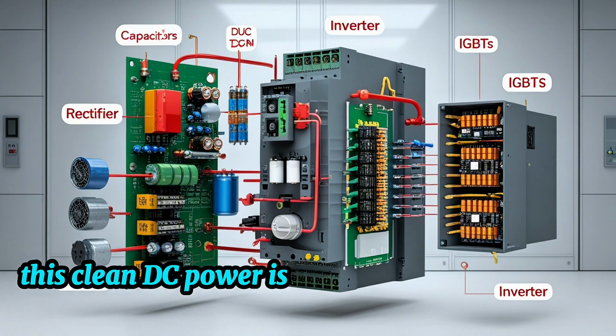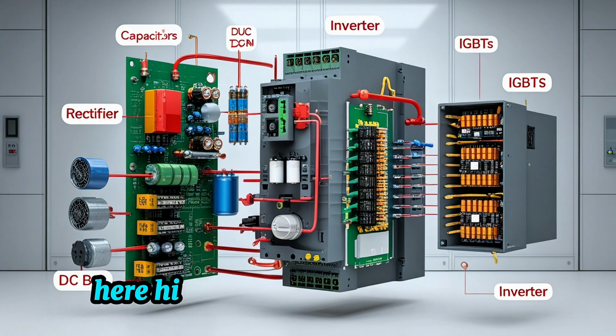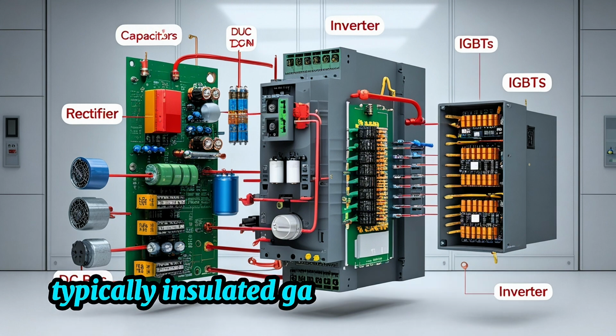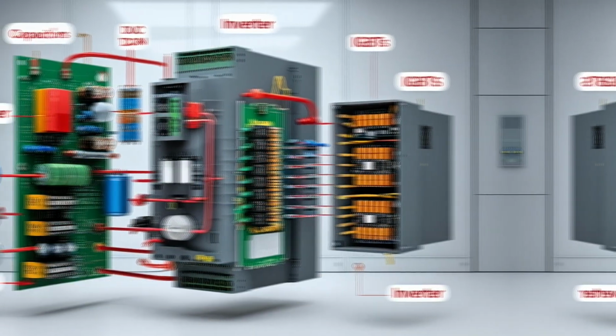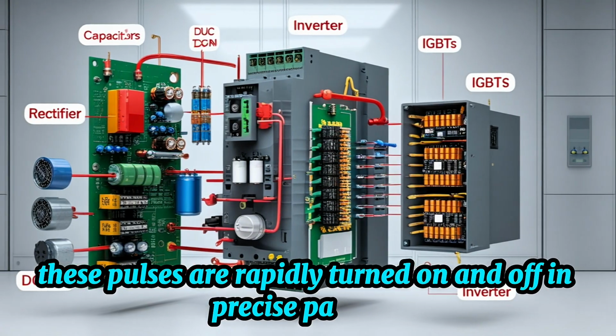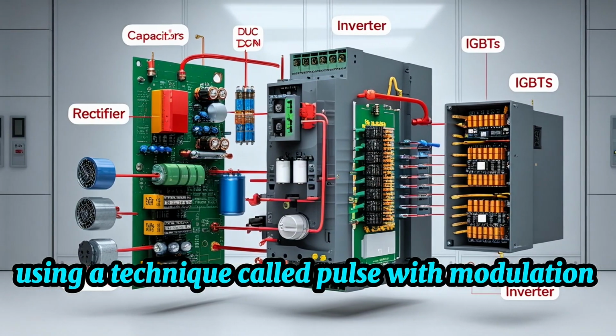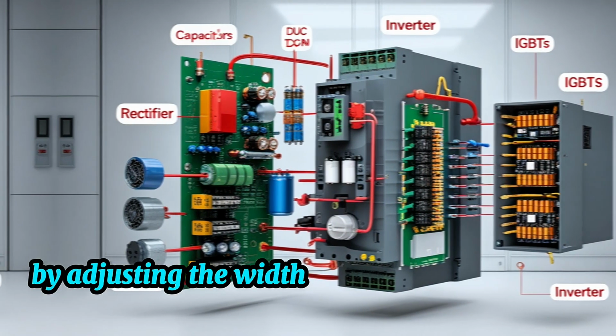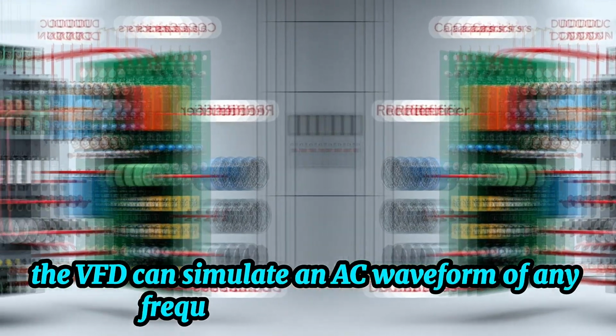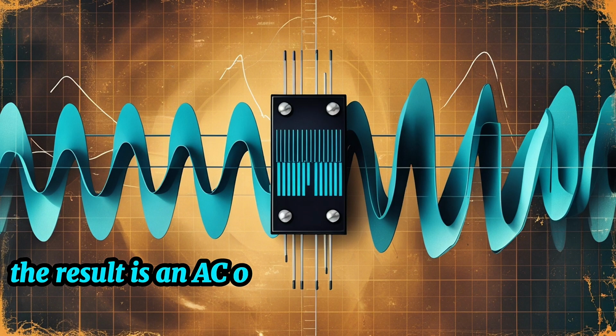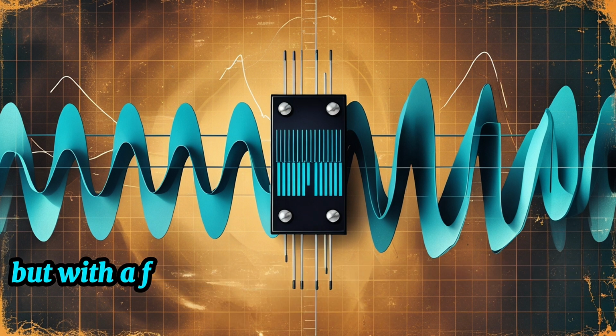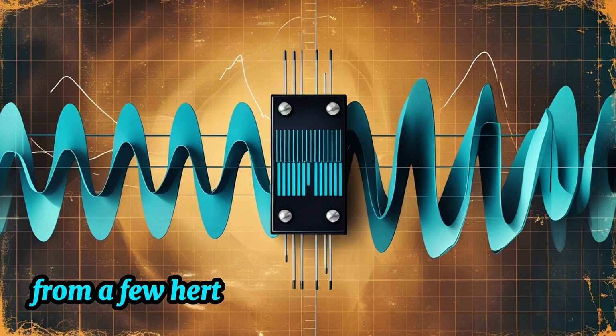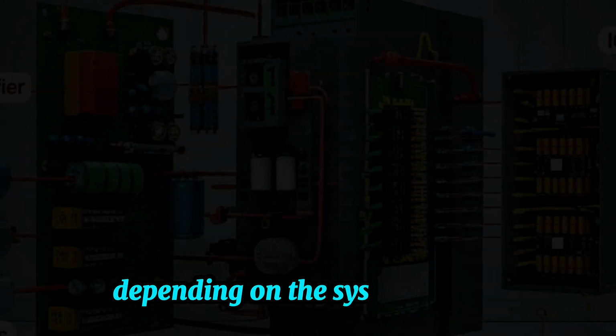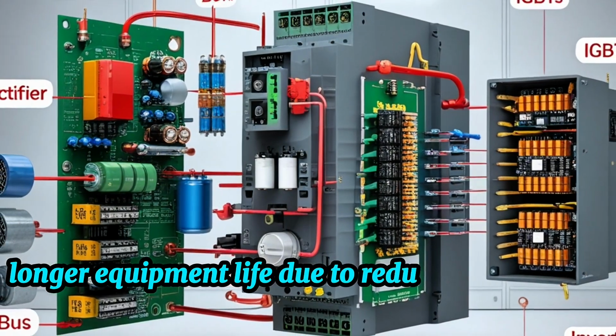This clean DC power is then fed into an inverter stage. Here, high-speed electronic switches, typically insulated gate bipolar transistors, IGBTs, are used to chop the DC voltage into pulses. These pulses are rapidly turned on and off in precise patterns using a technique called pulse width modulation, PWM. By adjusting the width, timing, and spacing of these pulses, the VFD can simulate an AC waveform of any frequency and voltage level. The result is an AC output that looks and behaves like a sine wave, but with a frequency that can be adjusted in real time, from a few Hz up to several hundred Hz, depending on the system design.